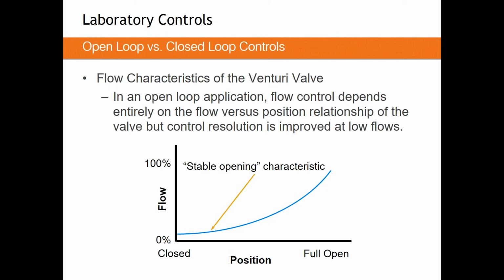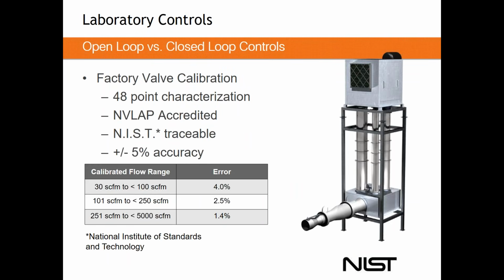If you really need that low flow and high controllability, the Venturi valve is going to be a little bit better at that. Now that being said, creating a Venturi valve is a whole lot harder than creating a closed loop style of valve. Every single Venturi valve needs to be tested. Every single one needs to be put on a highly calibrated rig and run through its paces of what position is equal to what airflow.